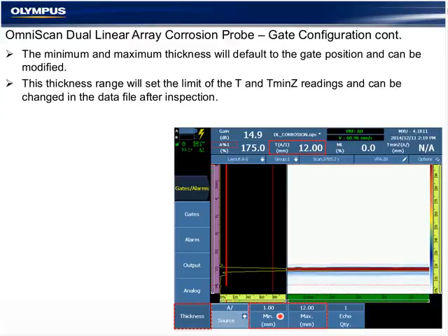By default, it will set to the width of the gate, and it is reduced by the operator. The number that appears in the thickness reading will not be outside the range of what is listed in the minimum maximum range here. And it's normal prior to inspection conditions to set this from 1 to the nominal thickness and adjust it later during analysis mode or when inspection conditions are known.